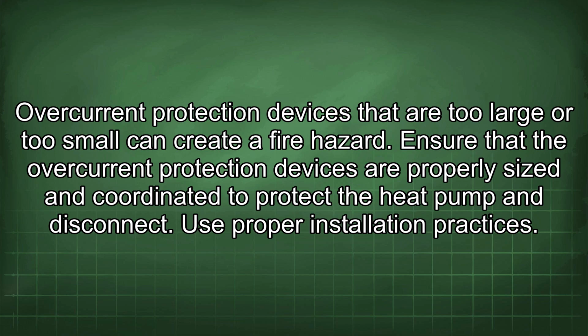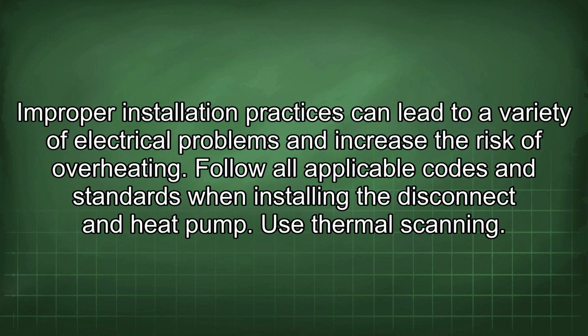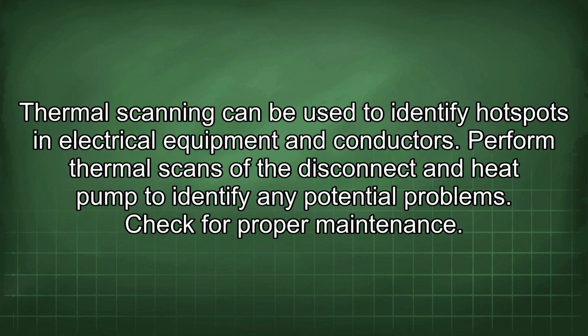Use proper installation practices. Improper installation practices can lead to a variety of electrical problems and increase the risk of overheating. Follow all applicable codes and standards when installing the disconnect and heat pump. Use thermal scanning. Thermal scanning can be used to identify hotspots in electrical equipment and conductors. Perform thermal scans of the disconnect and heat pump to identify any potential problems.